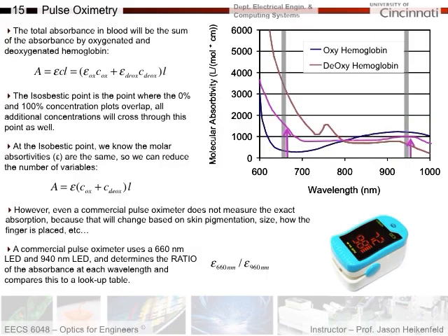The total absorption of the blood will be the sum of the absorbance of the oxygenated and deoxygenated components — total absorbance equals the oxygenated concentration term plus the deoxygenated concentration term, times the path length. What we can do is go to the isobestic point where the curves overlap, where the 0% and 100% concentration plots exactly overlap. At that point, the molar absorptivities are the same, so instead of having epsilon-oxy and epsilon-deox, we can use just one epsilon and simplify our variables.